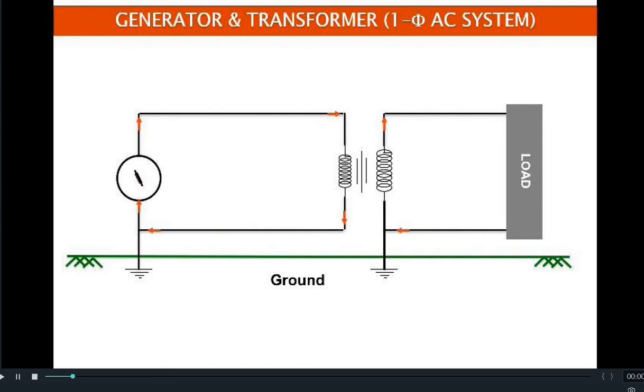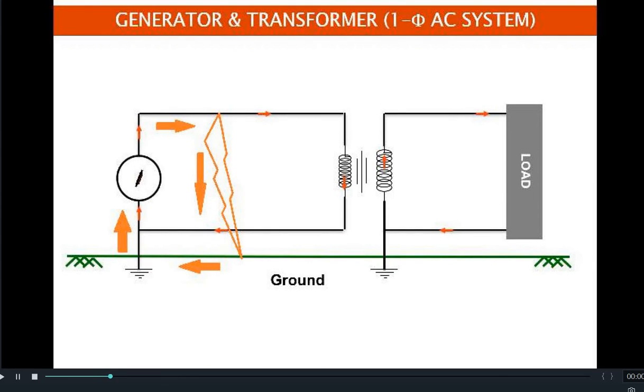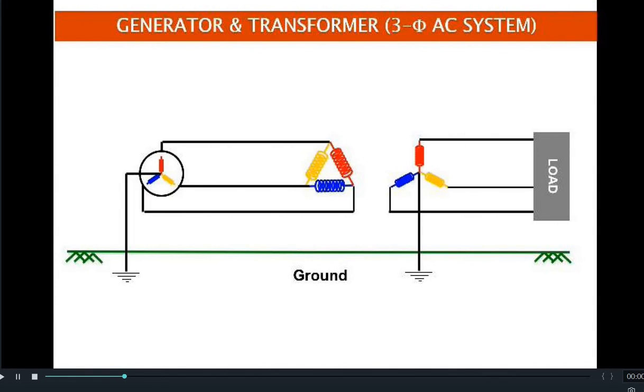In a single-phase AC system, there is a phase and a neutral. The neutral of the single-phase system is connected to the ground. Because of that, whenever there is a fault in the AC system, the current starts to flow towards the earth — it is not actually going to earth, it is going to the source through the shortest path. Due to the fault, the shortest path becomes phase to ground and then ground back to its source.